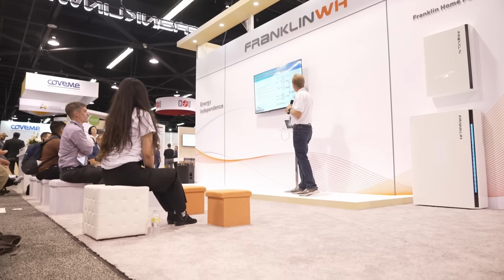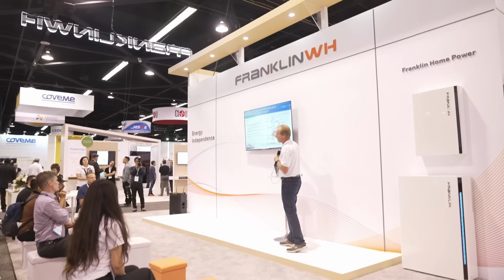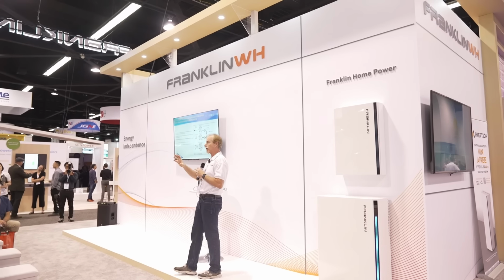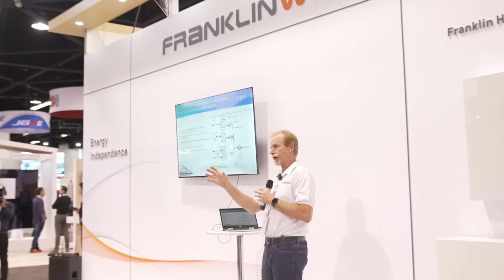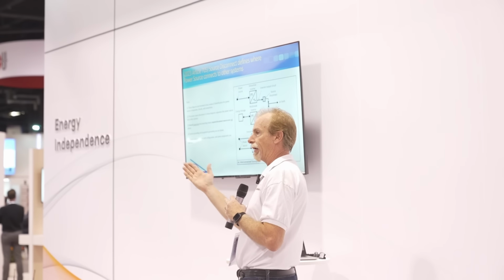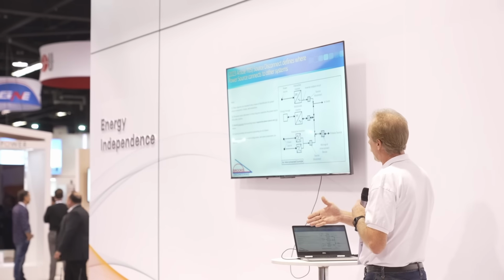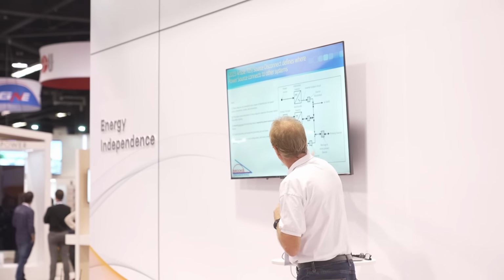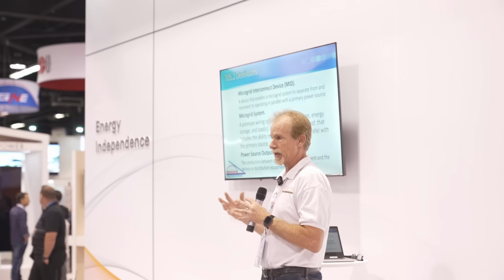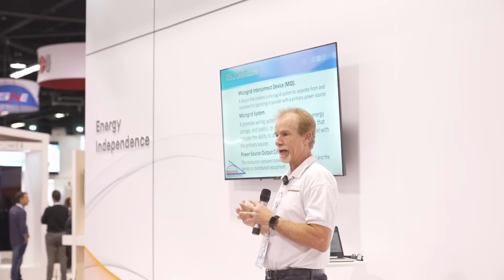And so, we have multi-mode inverters, and the whole idea behind a multi-mode inverter is you're shifting the inverter between two modes: current mode when you're connected to the grid, and voltage mode when you're disconnected from the grid. All other inverters have to follow the voltage mode inverter when you're in backup mode. So you could have microinverters, multiple inverters with different power sources connected into that. So microgrid interconnect device, that's a device that isolates and reconnects to the grid.